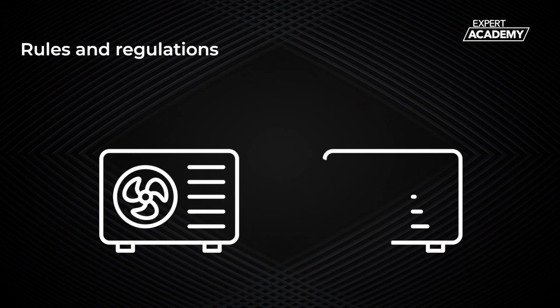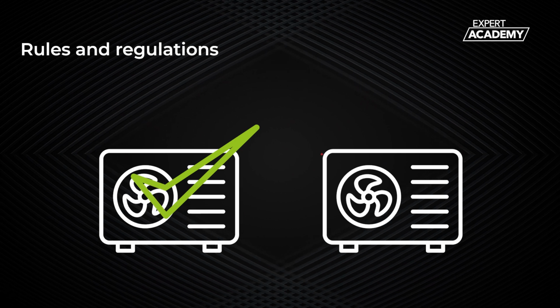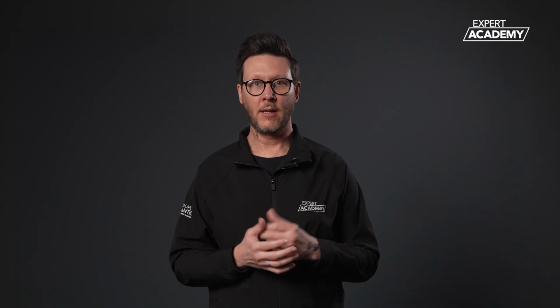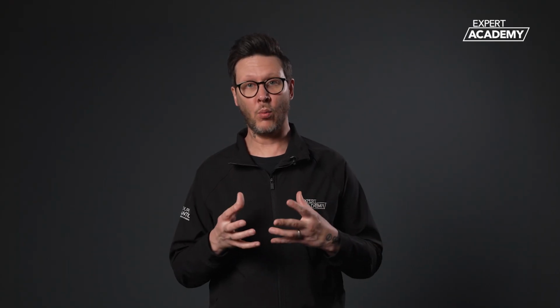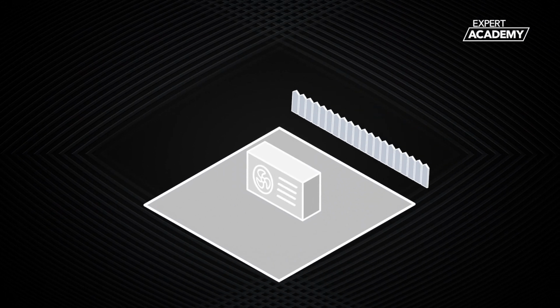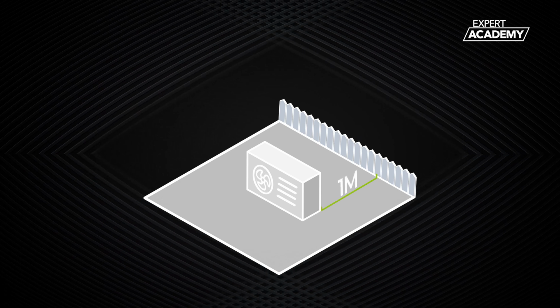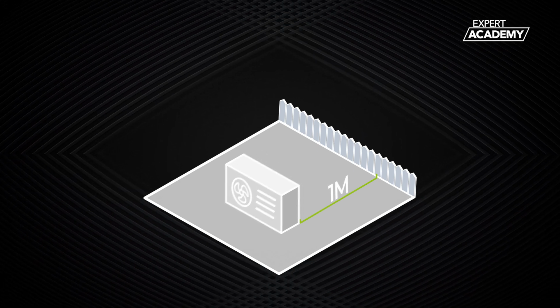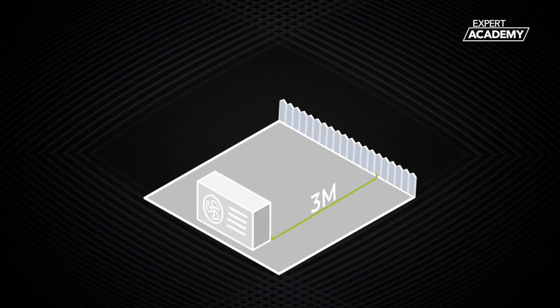Only the first installation of a heat pump at that property is classed as permitted development, meaning if the property was to need or want a second heat pump, there would be a requirement for planning permission. All parts of the heat pump must be at least 1 metre from the boundary for England and Scotland. This is currently 3 metres for installation in Wales.